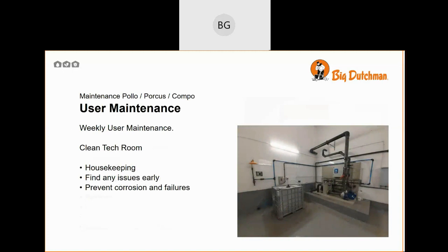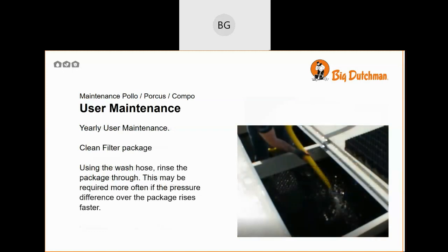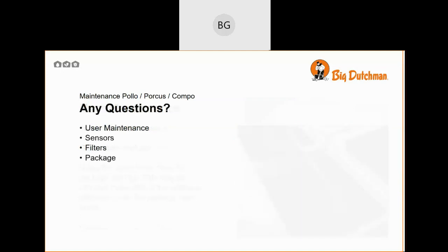Housekeeping. Cleaning of the tech room will make sure that you find any issues early. It will prevent corrosion and failures. Yearly maintenance. Cleaning of the filter package will be required at least yearly. However, using the wash hose to rinse the package through, this may be required more often if the pressure difference over the package rises faster. As I mentioned before, this should take about 45 seconds to a minute per meter square. Any questions on user maintenance, sensors, filter cleaning, package cleaning?